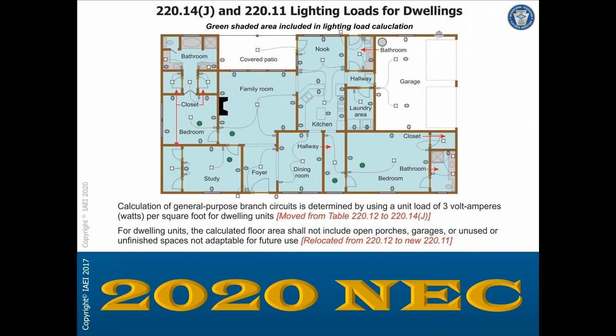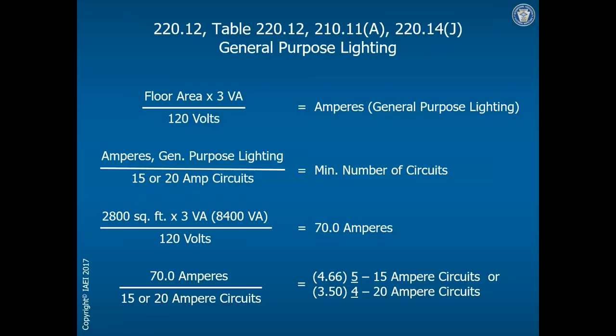There was a change in the 2020 NEC that you need to be aware of. In the 2017 code, to get that 3 watts per square foot, you'd go to Table 220.12, where dwelling units were listed. In the 2020 code, that table was renamed and reserved for non-dwelling unit loads — you'll still find wattage per square foot for warehouses, churches, and similar occupancies there. But the 3 watts per square foot for dwelling units was moved to section 220.14(J) in the 2020 code. The values and calculation remain exactly the same; only the location changed.